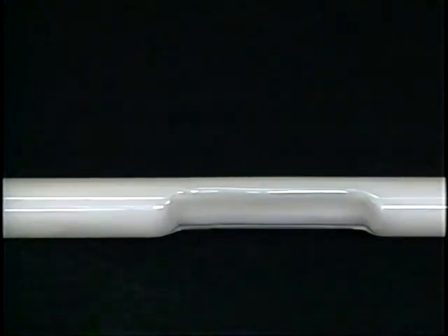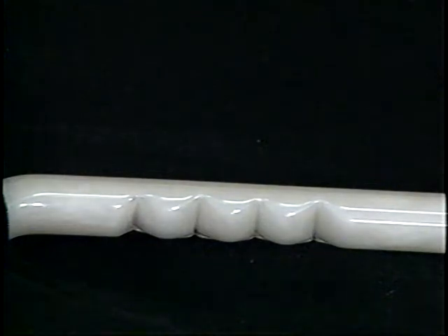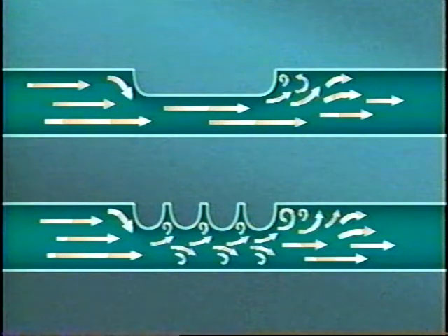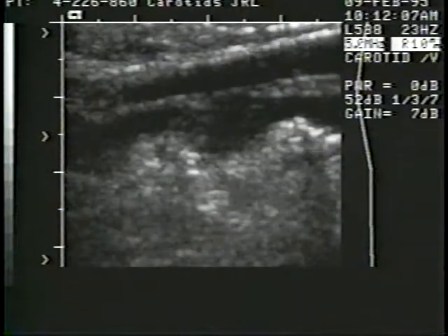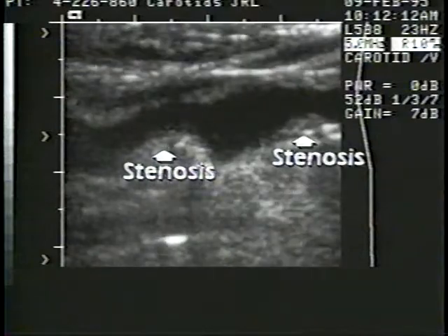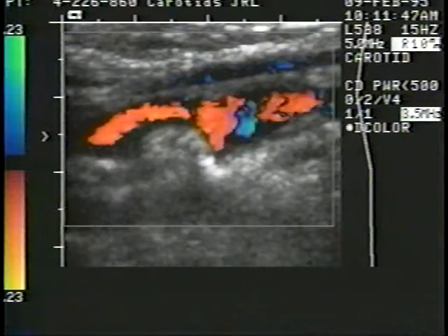Module 7 demonstrates a single stenosis versus multiple stenoses in a series. A flow rate setting of medium is optimal. Multiple stenoses occurring in a series will have a more pronounced effect on distal pressure and flow than a single lesion of equal length. This occurs because large amounts of energy are lost at the entrance and exit sites. This segment demonstrates a single long lesion in comparison to a lesion of similar length with multiple entrances and exits. There is grossly disturbed flow with turbulence at each exit.